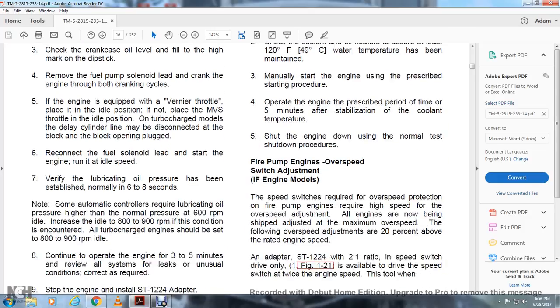Fire pump engine overspeed switch adjustment. The speed switch is required for overspeed protection of the fire pump engine, which requires a high speed for the overspeed adjustment. All engines are now shipped adjusted for the maximum overspeed. The following overspeed adjustments are about 20% above the rated engine speed.